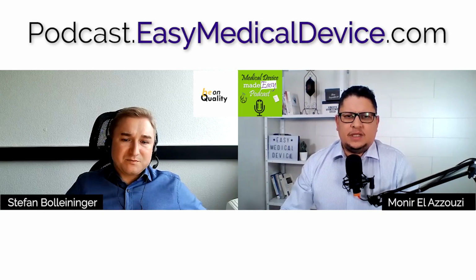So first thing, when you think something smells fishy, look into it. If 2017/745 or 746, for EU MDR or EU IVDR, is in it, then you should keep your eyes up. It looks weird if it's relevant to you. In case both tags are not included, then you can push it aside. Maybe it's for toys, maybe it's for cars, whatever. A common specification is a general concept which can be used for many other regulations.